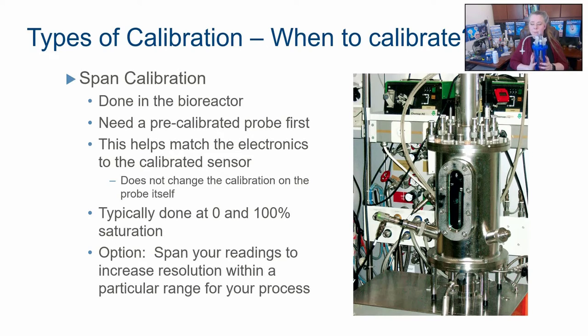How do I do a zero cal if I'm in a liquid environment? There are two options, and it depends on the bioreactor. The easiest in the world option on some bioreactors is disconnect. It says, do you want to do a zero cal? You're like, yep. And you disconnect the cable so that your cable is not actually attached to your probe. And you say, there's my zero cal. It's totally legit if your bioreactor accepts it, because 0 volts is 0 volts. And 0 oxygen should be what? 0 volts.